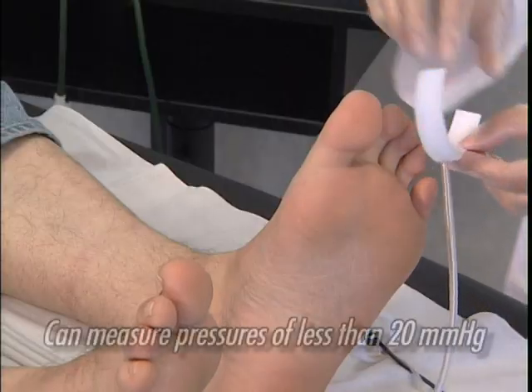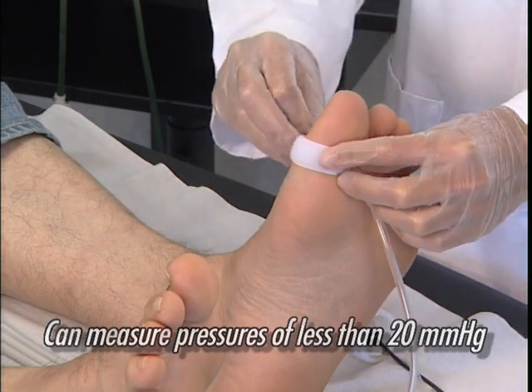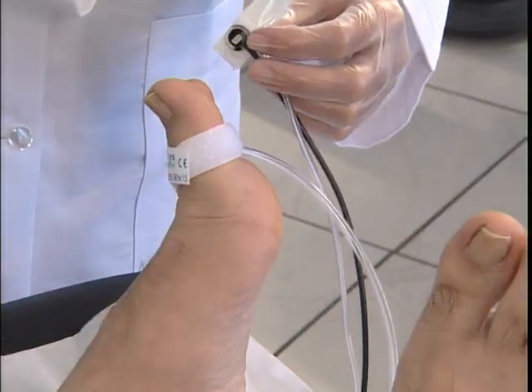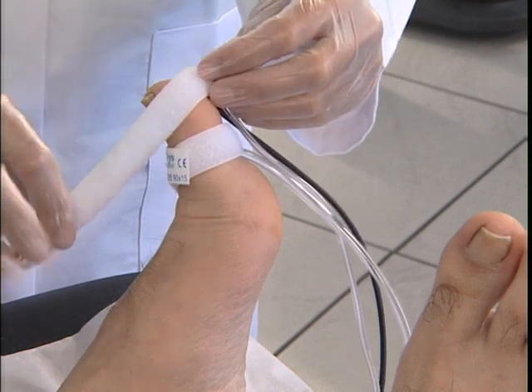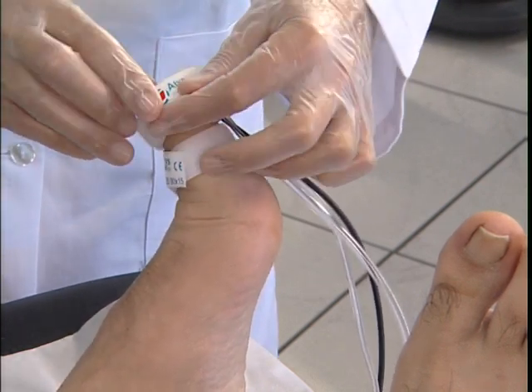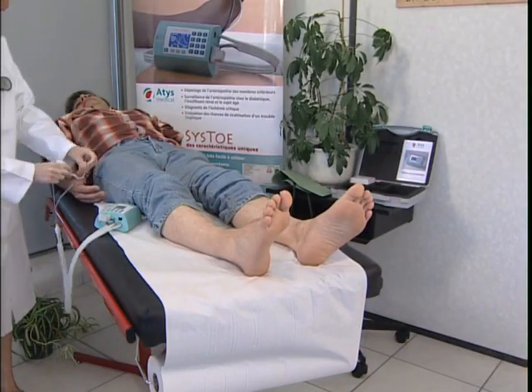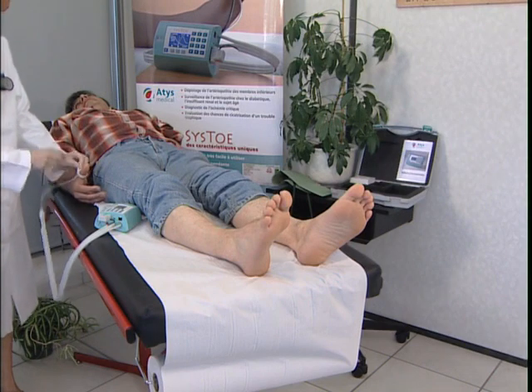The device is very sensitive, being capable of measuring pressures of less than 20 mm mercury. The SysToe system has been validated at the vascular testing department of Nîmes University Hospital. The SysToe can also be used to measure systolic blood pressure in the fingers.